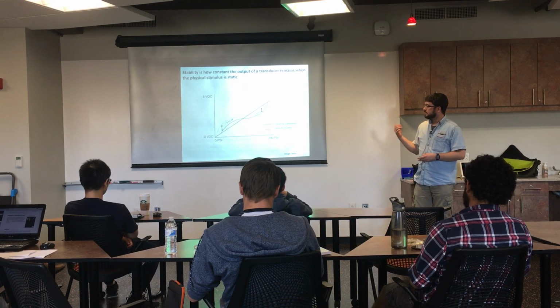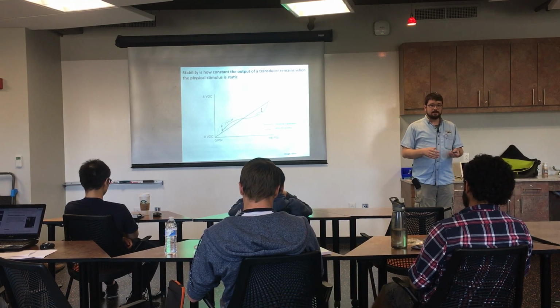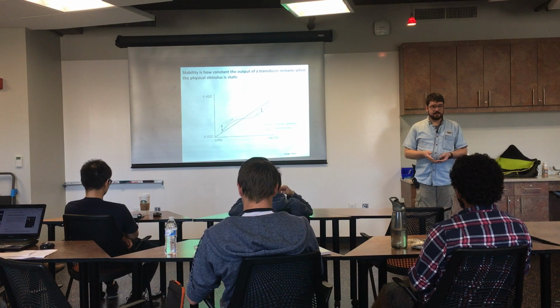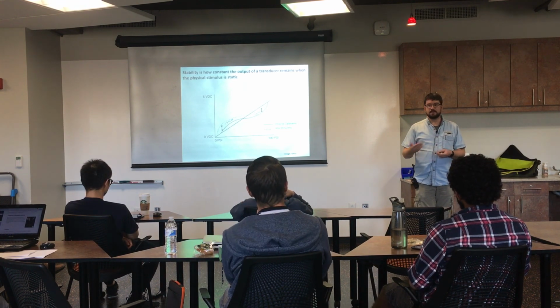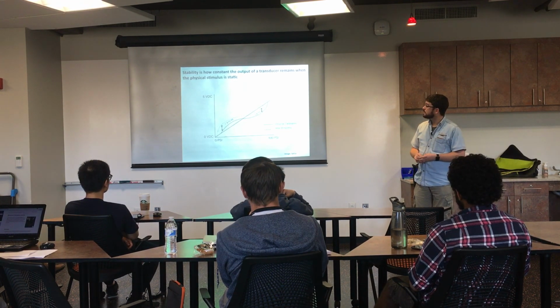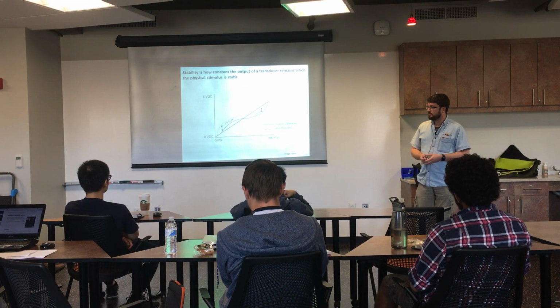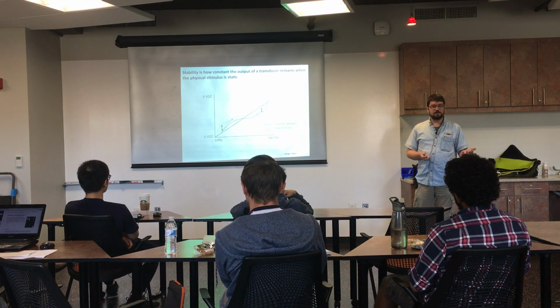In the lab, we try to calibrate things, have in the past anyway, semi-annually, which is a pretty standard calibration cycle. Semi-annually to annually is relatively standard for a lot of transducers. But if you have something in the field, say a seismometer, you may not be able to get to it very often.